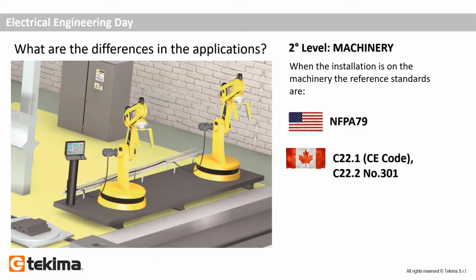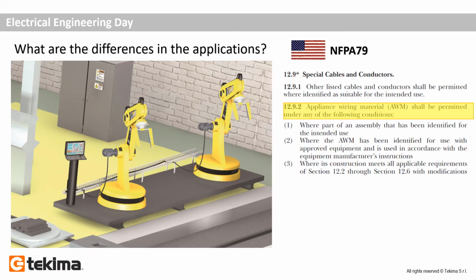Second level, machinery. As we have mentioned before, there are two main standards: NFPA 79 for the USA and C22.1, C22.2 number 301 for Canada. What does the norm say regarding the wiring methods? In NFPA 79, in point 12.9, special cable and conductor, you can find all the answers.